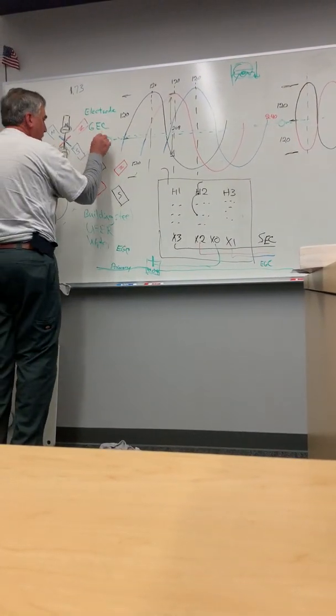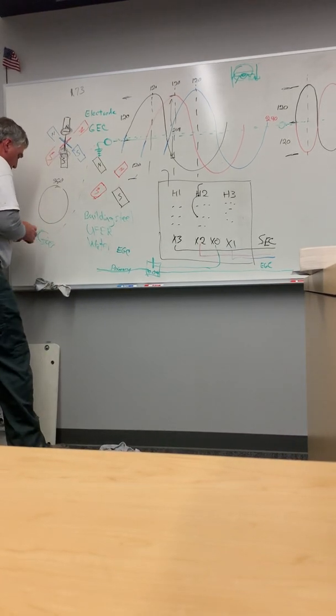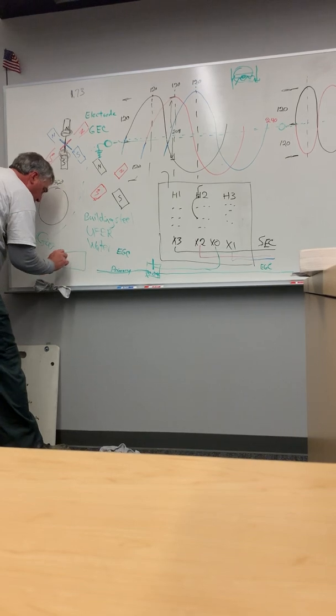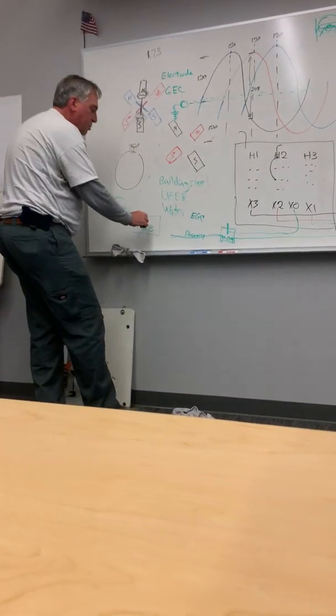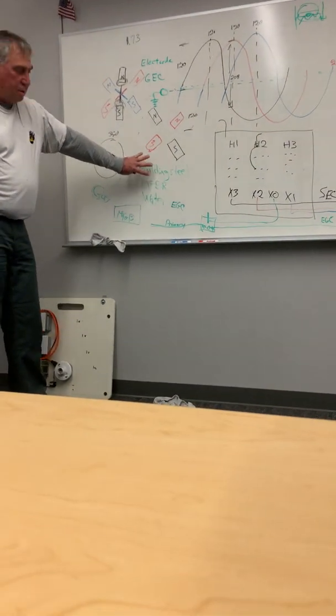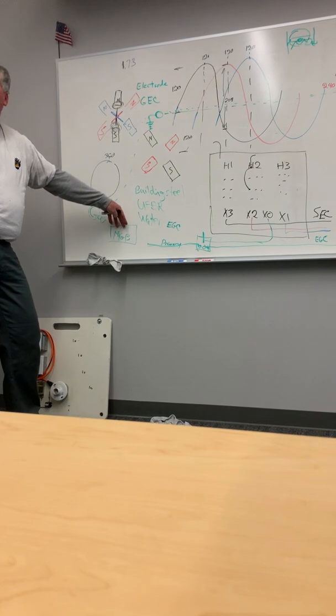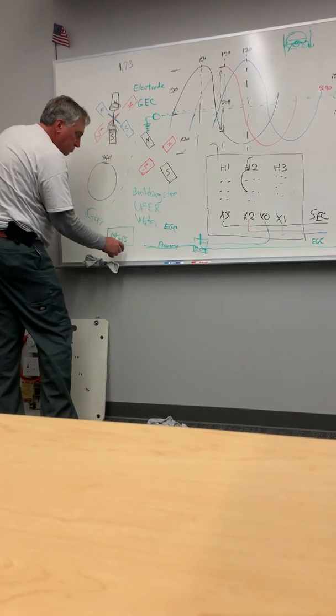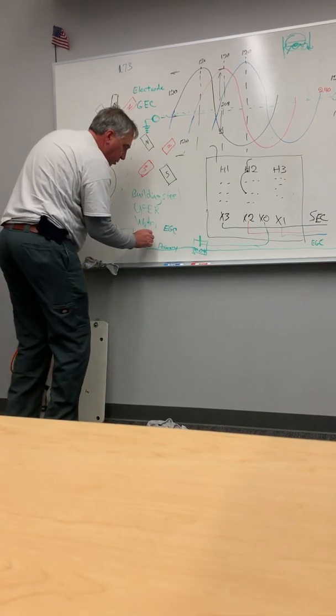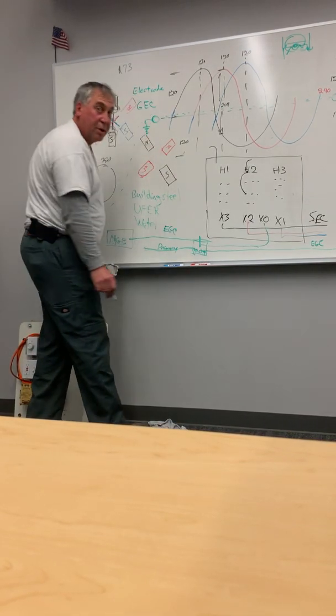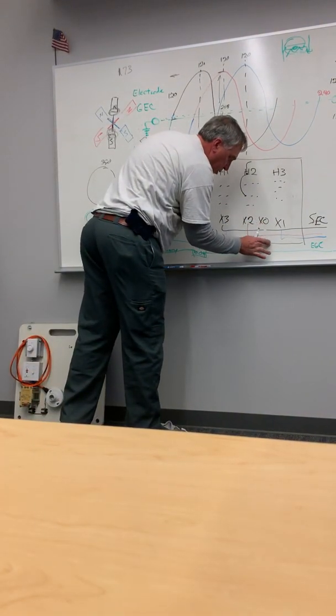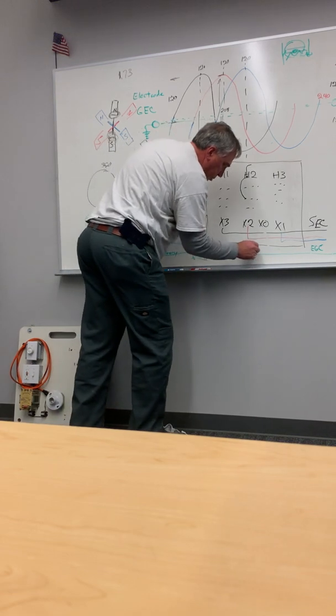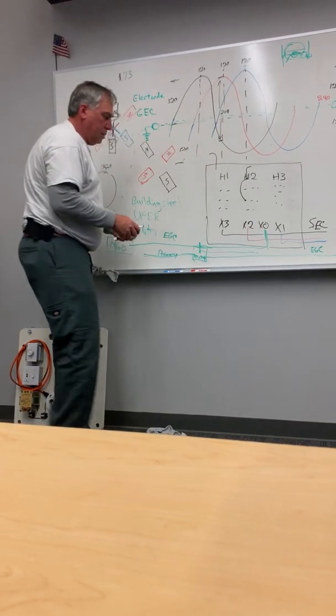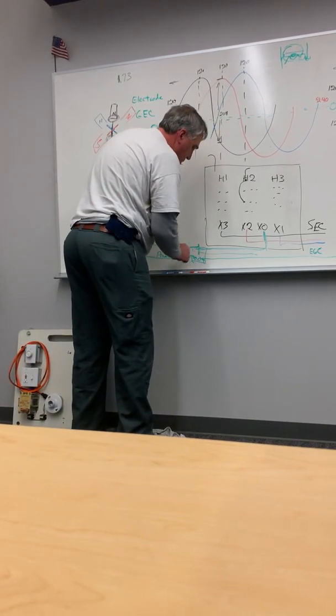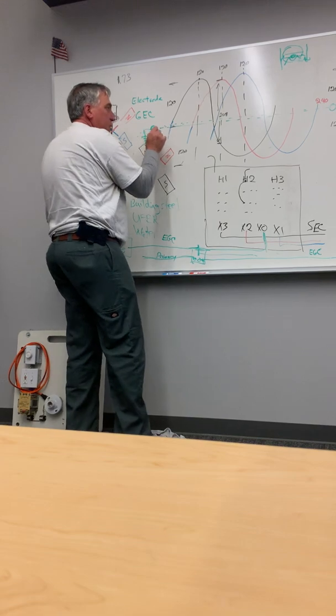Okay? So now the next thing we want to talk about is this grounding electrode conductor. It's going to come from a main ground bar in the electrical room. And we're going to create this main ground bar by taking all the things that we talked about here and putting them on this ground bar. So all of it is the same, right? And then we're going to take it into this transformer. We're going to lay that lug in there, we're not going to break it. And then we're going to bring it over here to this X0. That's the one we don't break; we take it all the way through, right? Because we're establishing what I call the zero point.